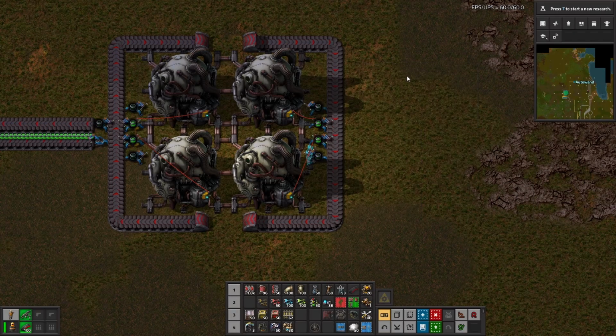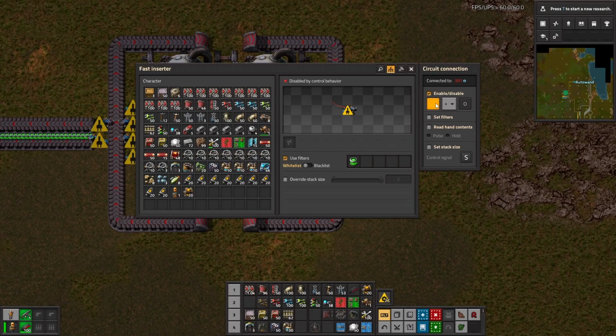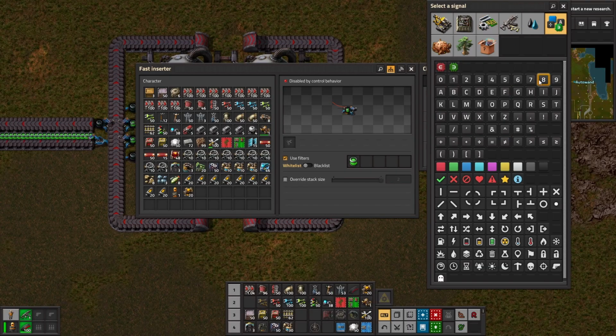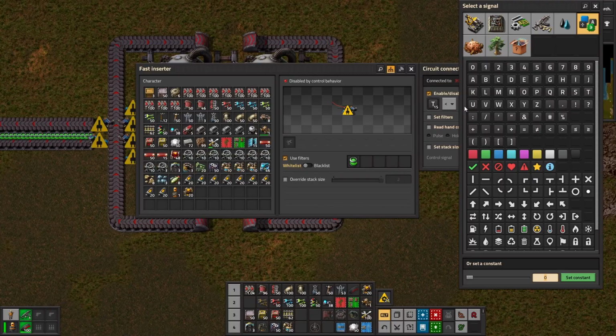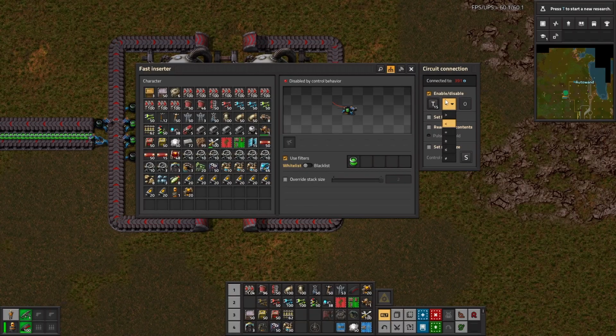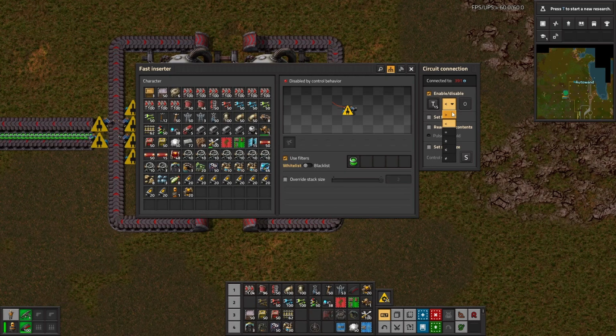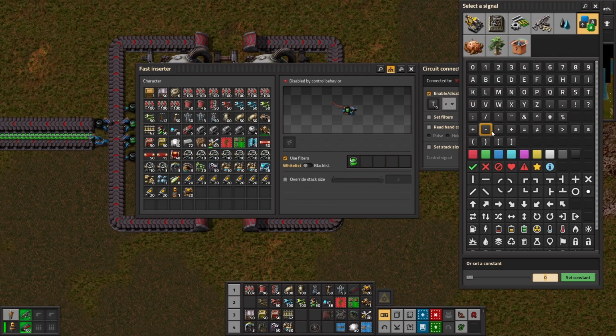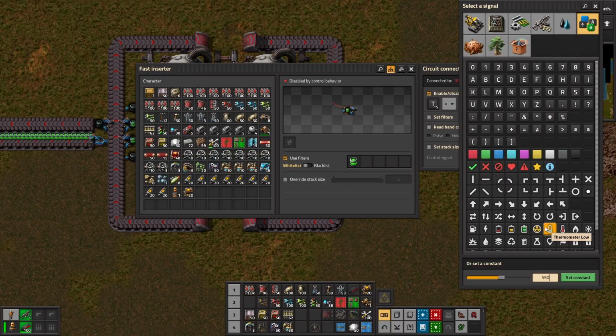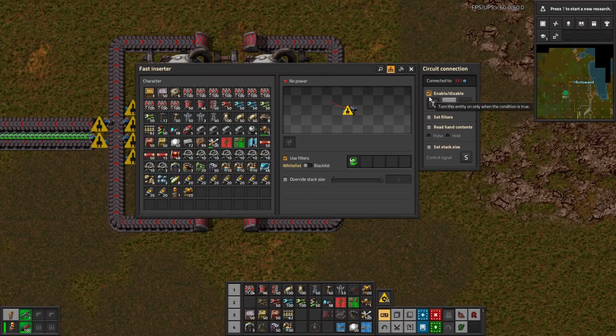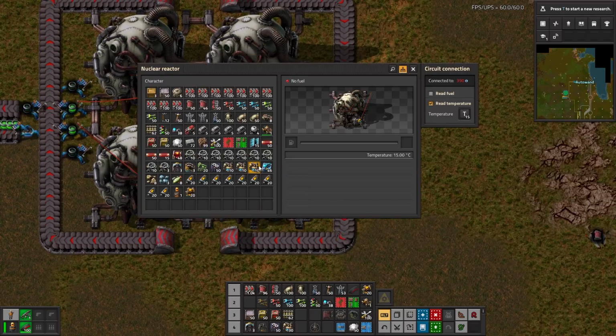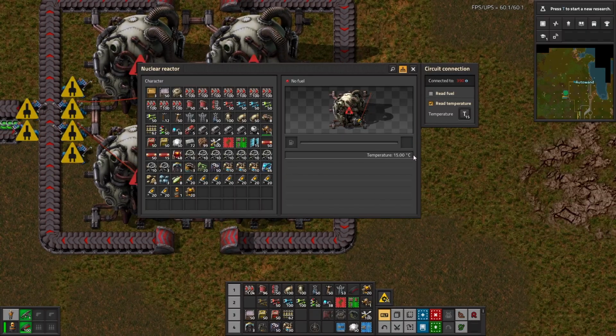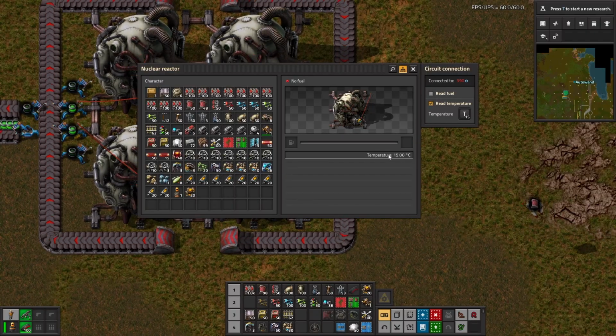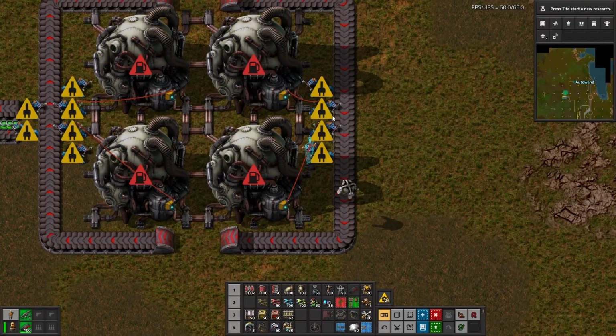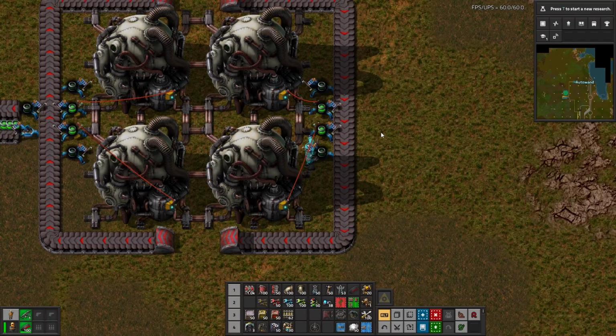So we're aiming for T, and we're going to set these to enable if T is less than 550. We're going to stay on the safe side. So as the temperature rises to 1,000 with the fuel, it'll start to settle down, and once it gets down to 550, these activate and insert fuel.